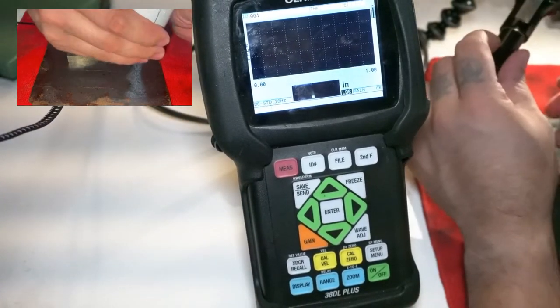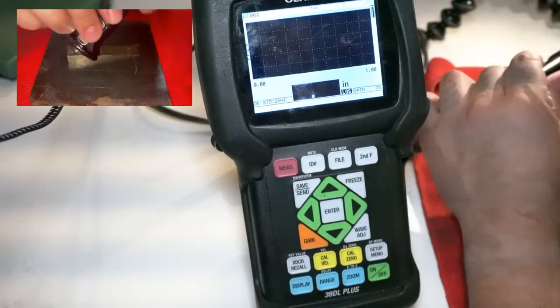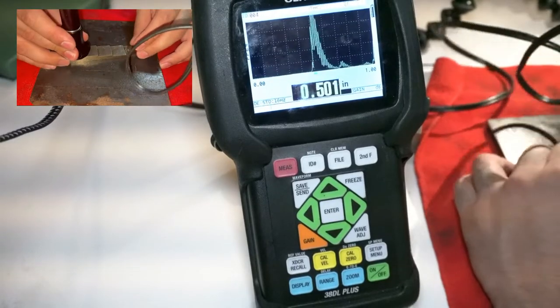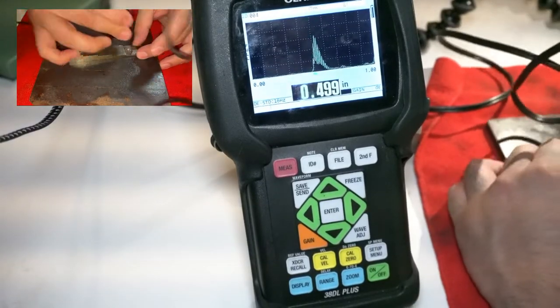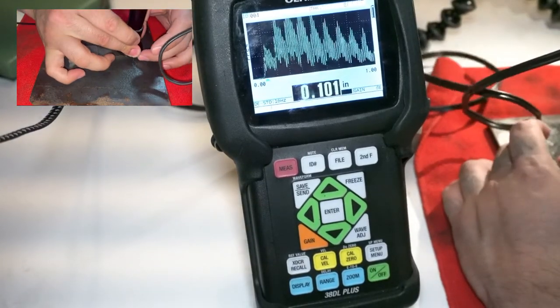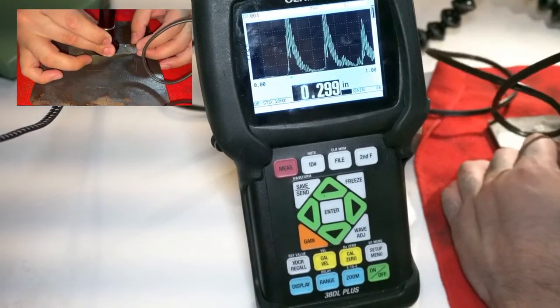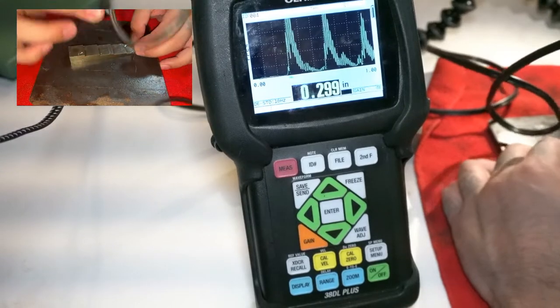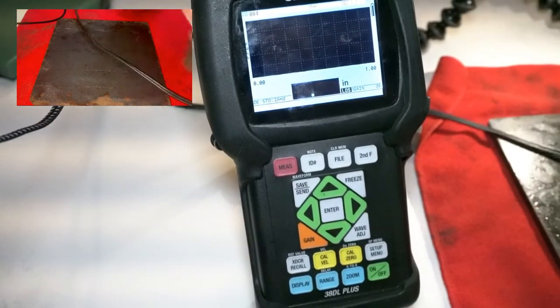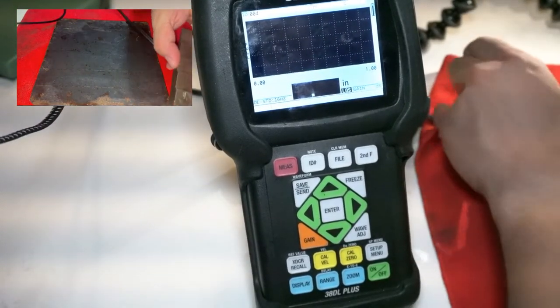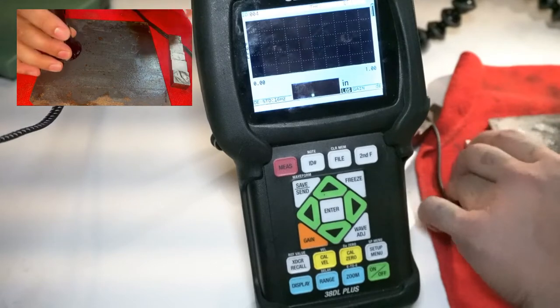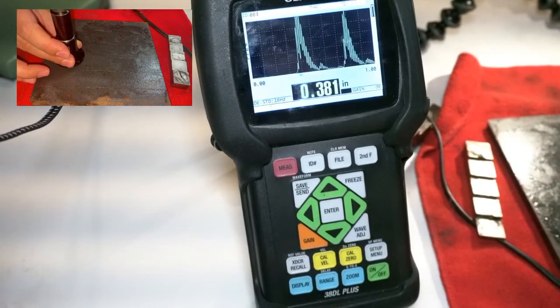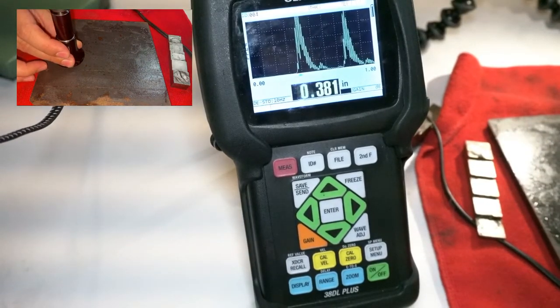I'm gonna go ahead and validate our calibration here. CalZero earlier on, everything looks really good. One of the things that you'll notice is that that gain came in really high.